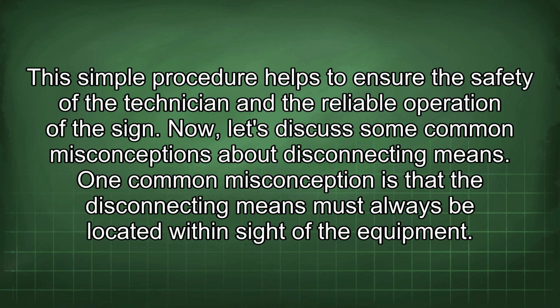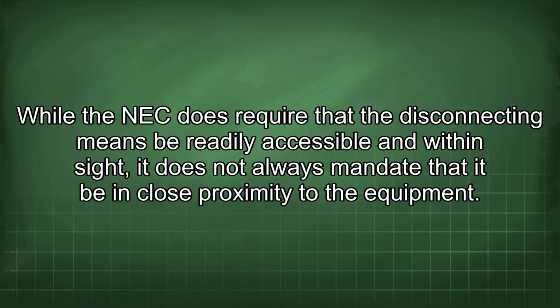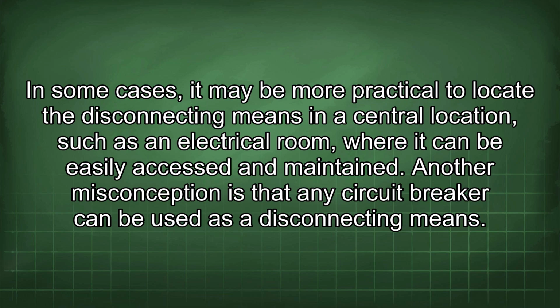One common misconception is that the disconnecting means must always be located within sight of the equipment. While the NEC does require that the disconnecting means be readily accessible and within sight, it does not always mandate that it be in close proximity to the equipment. In some cases, it may be more practical to locate the disconnecting means in a central location such as an electrical room, where it can be easily accessed and maintained.